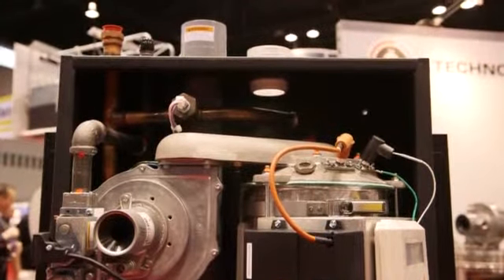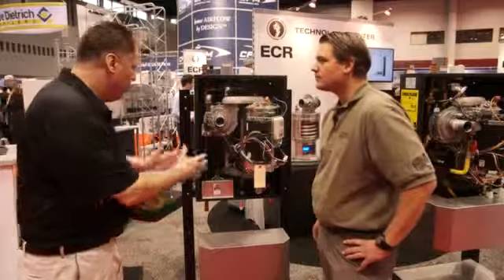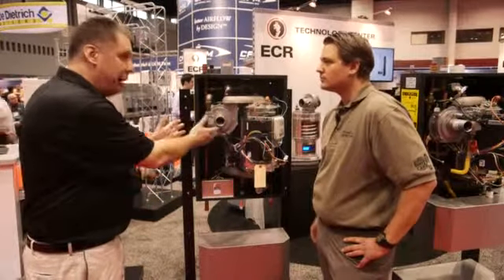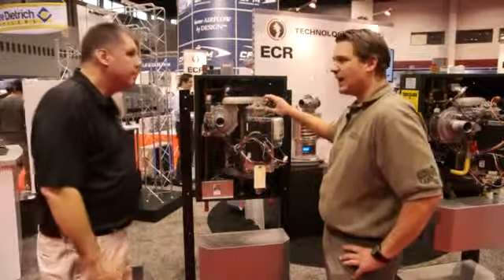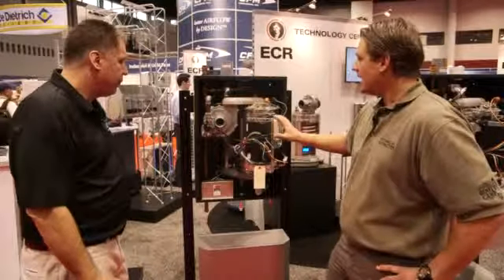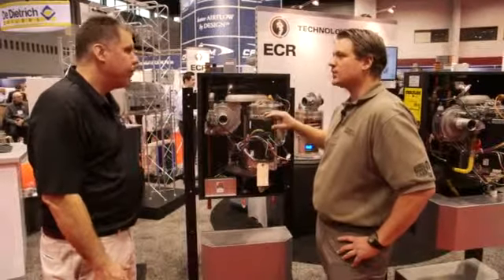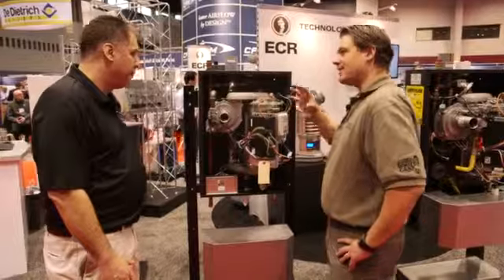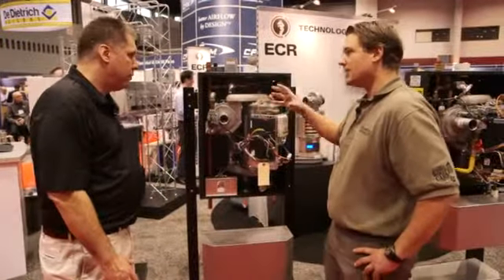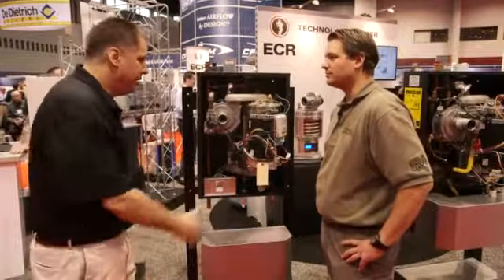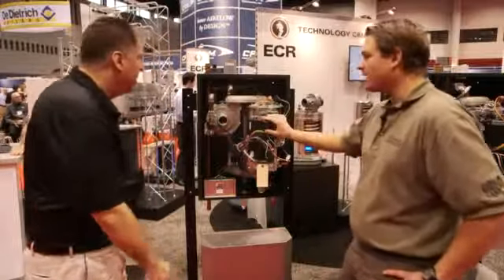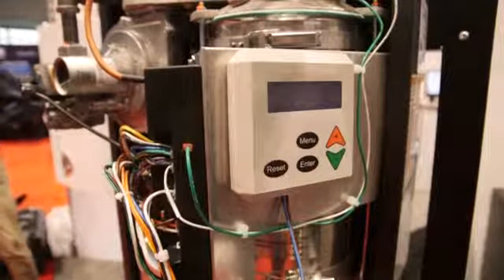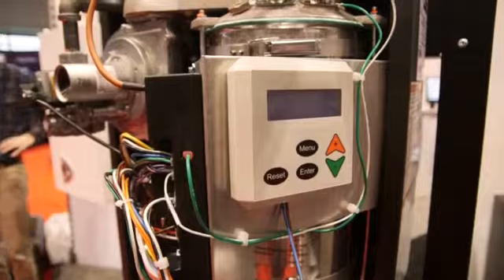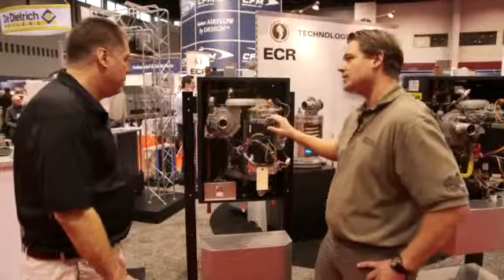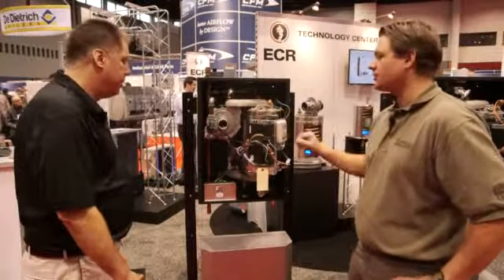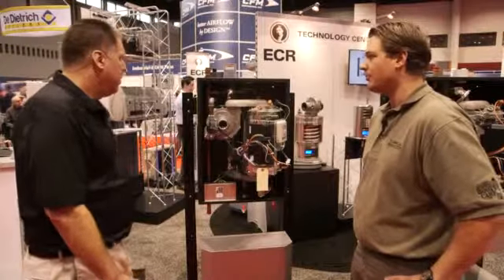So you've taken away the primary, secondary, kind of cleaned it up. What other features is this? Has the same stainless steel heat exchanger? It's the same heat exchanger design. It's the same control platform. It's just an entry-level model, so it's a little bit less expensive than our SSC version, which is our top of the line model. But it does have the same control. Same control package, still 95% efficient. It has the same Argus Vision control readout on the side here. So if the contractor's used to the SSC, he could still try one of these out and it would be the same platform.